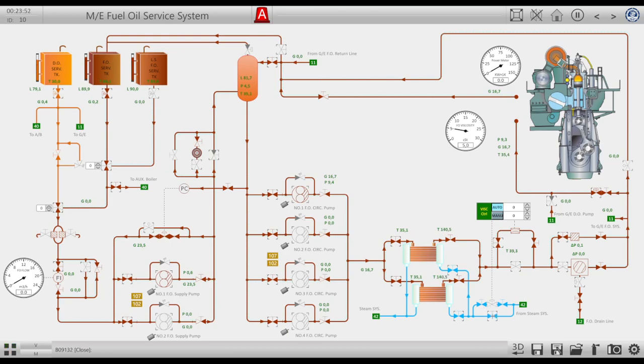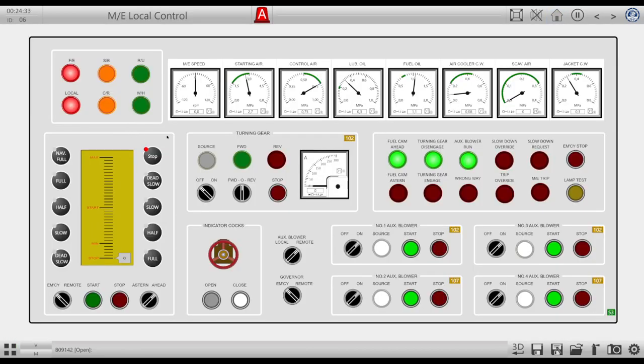Let's try to open this bypass valve. Then indeed we have a rise in pressure, so we do have steam. But for some reason, apparently it is necessary to heat up the heavy fuel at this moment. Fuel is going back to this mixing tank. The mixing tank is filled via the main systems. I'm going to start the second pump. Let's see if it now picks up some temperature. Yeah, leave it for now and we'll visit it again later on.